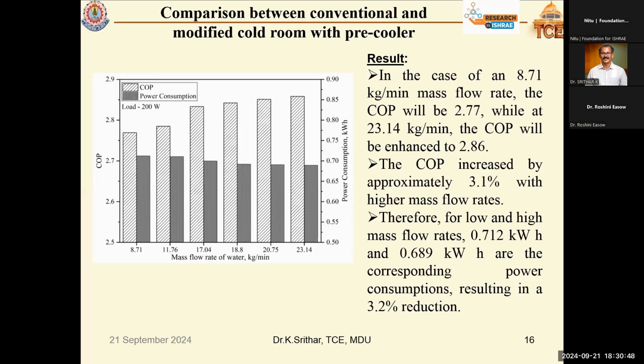Based on power consumption, the lower mass flow rate consumes 0.712, whereas the higher mass flow rate consumes 0.689. That is the power saving we are getting. So based on the result, a higher mass flow rate of the pre-cooler will give you a better COP as well as lower power consumption, about a 3.2% reduction in power consumption.